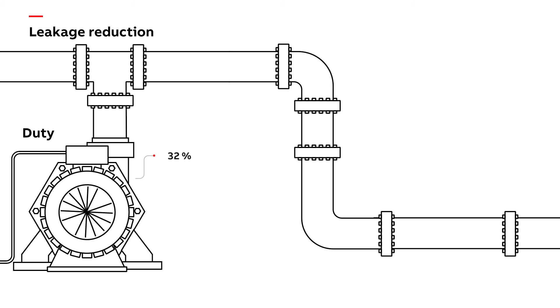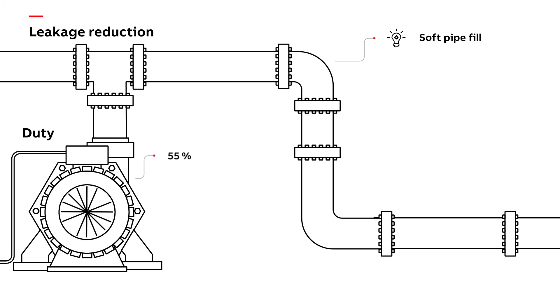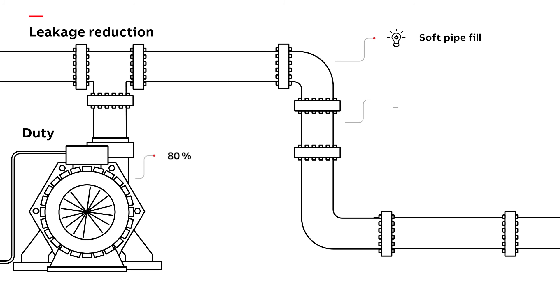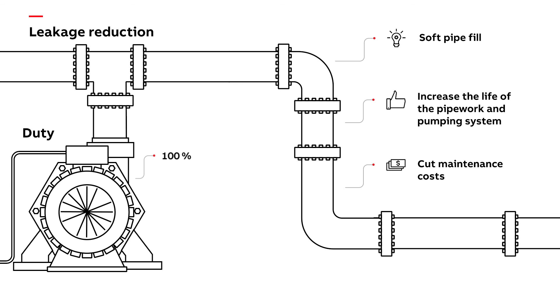The use of drives allows the user to gradually ramp the acceleration of the pump at a safe rate. A soft pipe fill feature allows a smooth build-up of flow into pipes. The lifetime of the pipework and the pumping system is therefore increased.